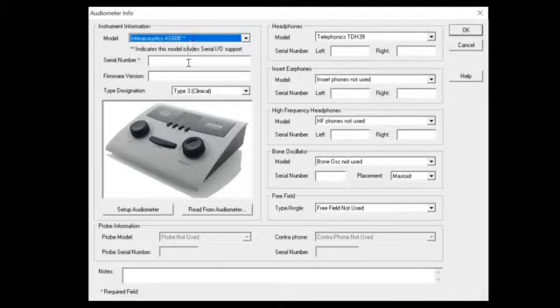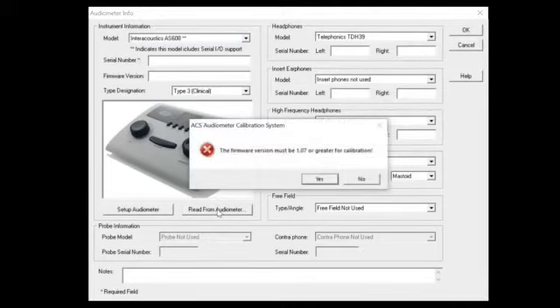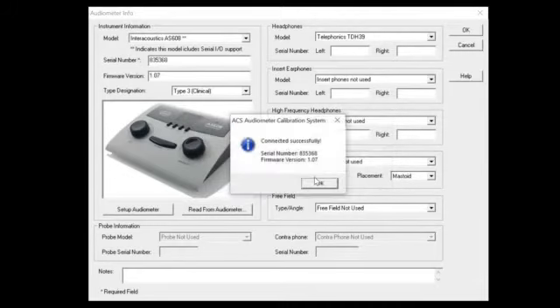Now, we have to put in a serial number, and we want to put in for both the headphones and the audiometer. But because it's an interface, if that data is stored in the audiometer, all I have to do is come down here, click on this. It gives me a warning that if it's not firmware version 107 or greater, we can't do the calibration. Well, let's see. It makes a successful interface, and populates the serial number into that field and the firmware version.